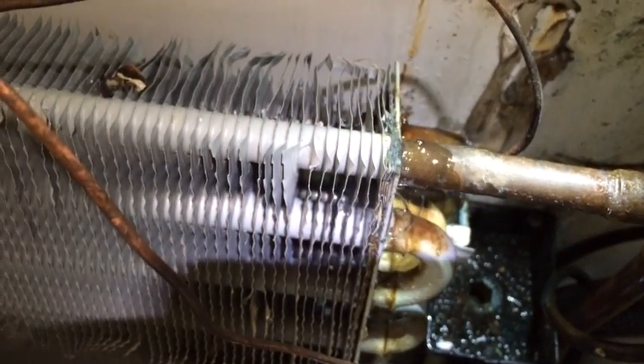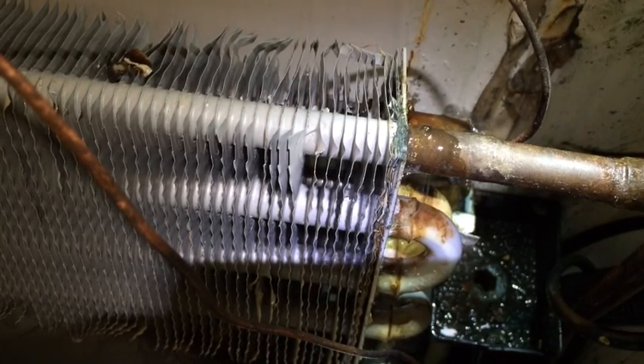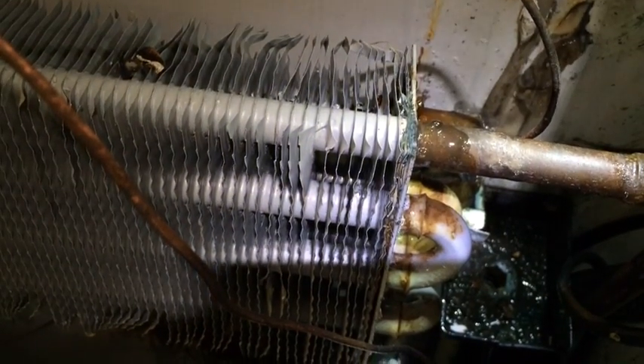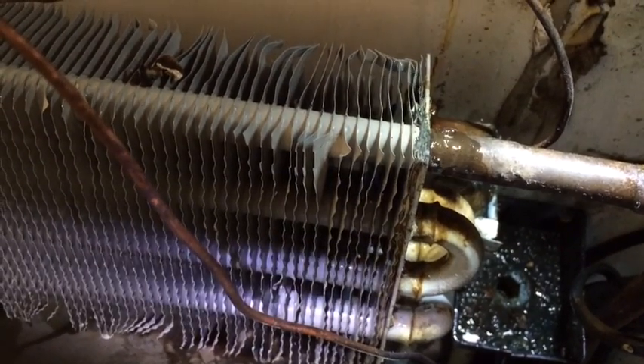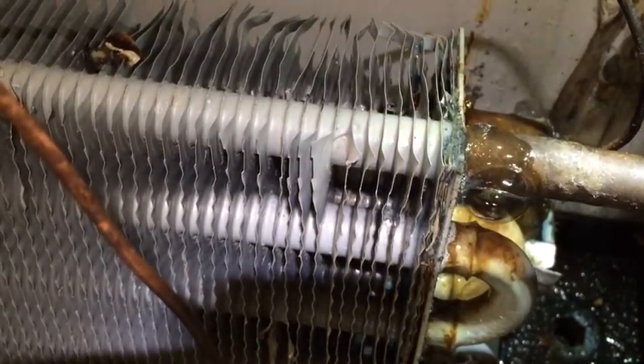She's making little bubbles, right there. That's with very little R134A in the system and a bunch of nitrogen, and it found that little leak. That's how small the leak was.